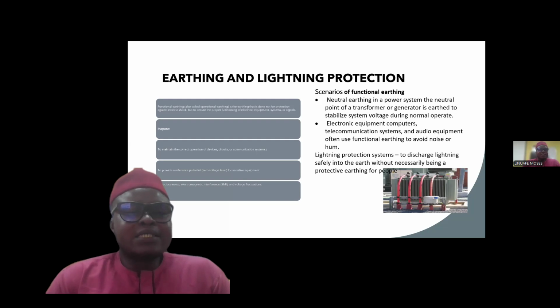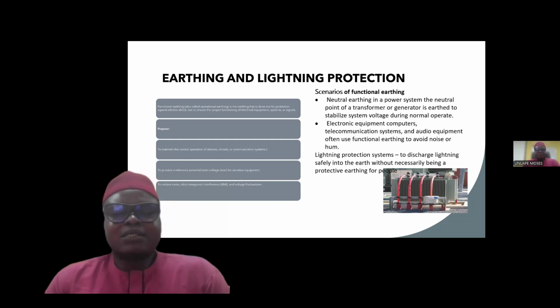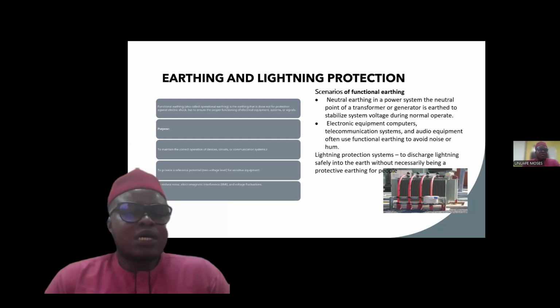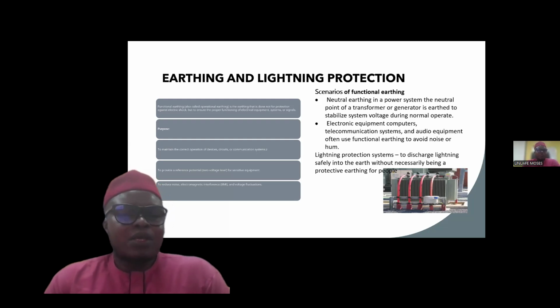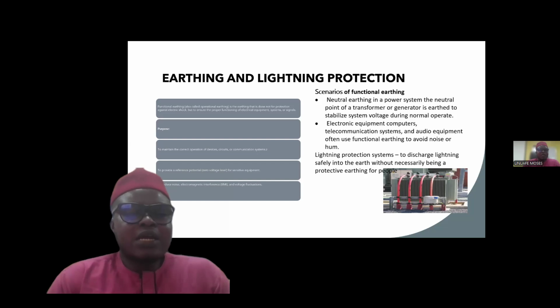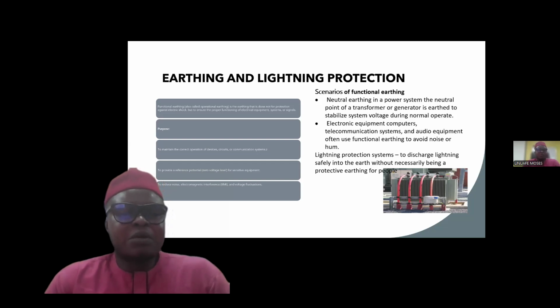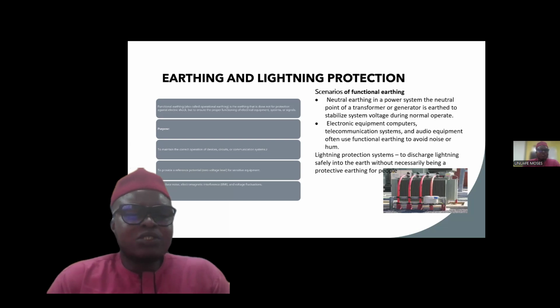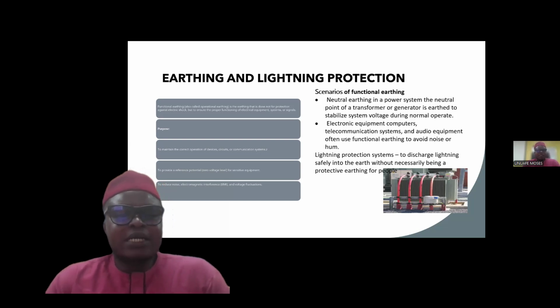To maintain this, there is a reason for us to do this. And what is the reason? It is to maintain a correct operation of a device or circuit or communication system. Another reason is to provide a reference potential, like maybe 0 volt for a sensitive equipment. And the second reason is to reduce noise or electromagnetic interference with some equipment, especially communication equipment.